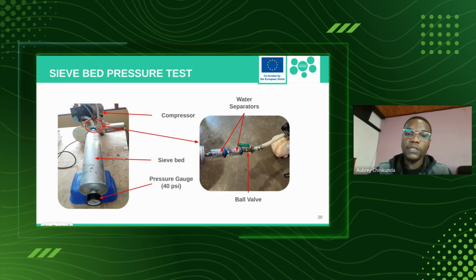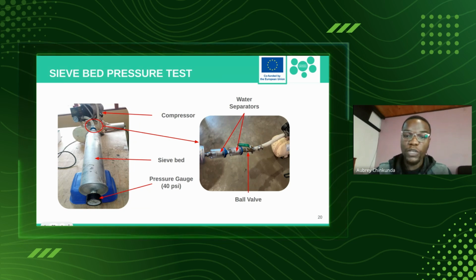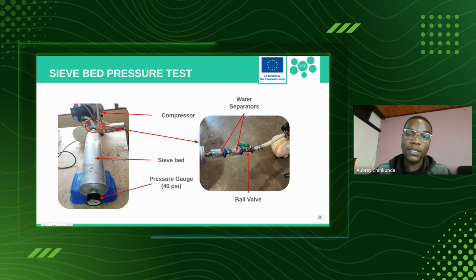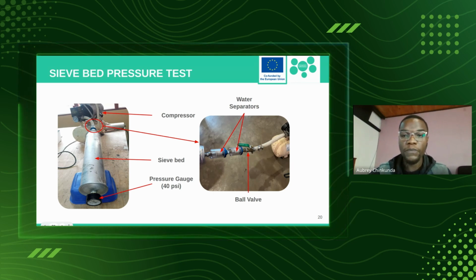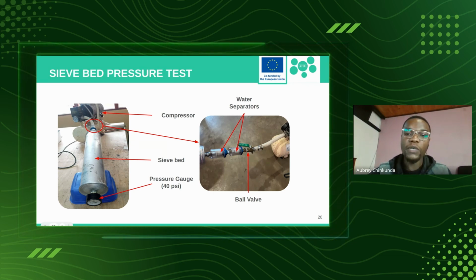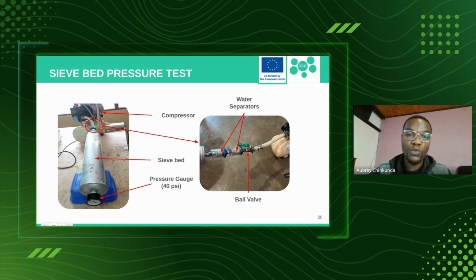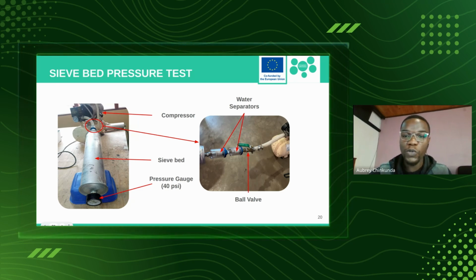If there are no leakages, then you slowly remove the sievebed. You need to be careful, again, because now you're dealing with pressure. 40 psi can still be dangerous. So you need to slowly bleed off that air until all the air is gone out of the sievebed, and then you can seal it. So after it passes the test, we pack it, we seal it, and we put it in the OpenO2 mobile workshop, which my colleague is going to talk about in the upcoming slide.